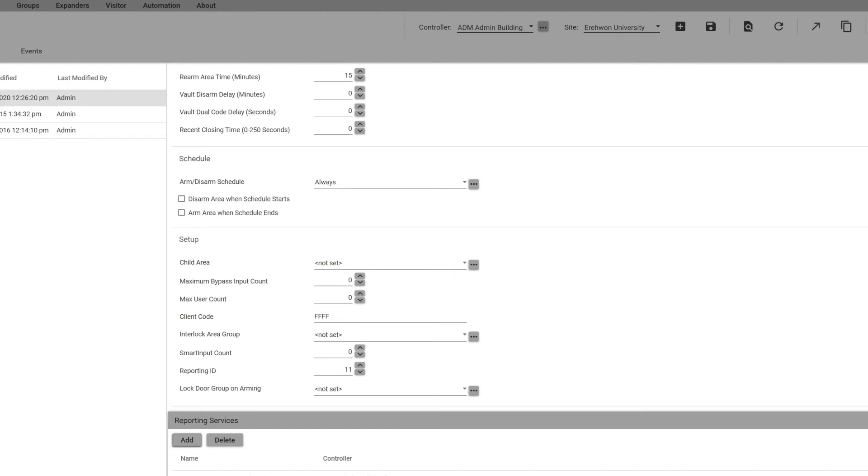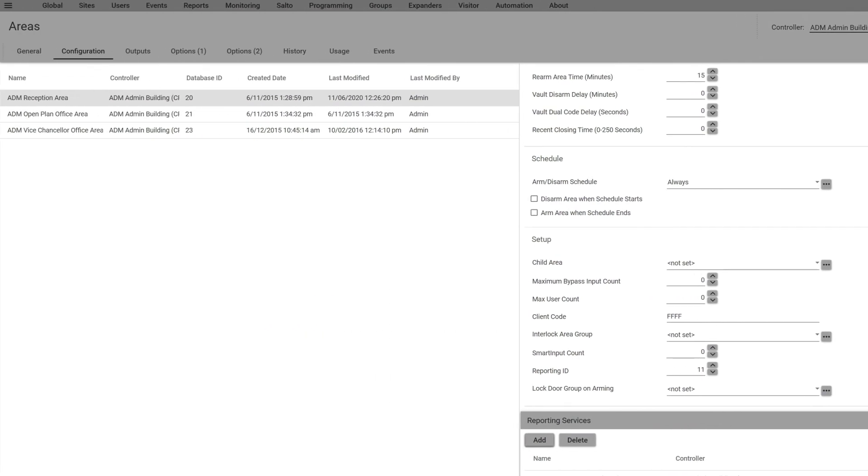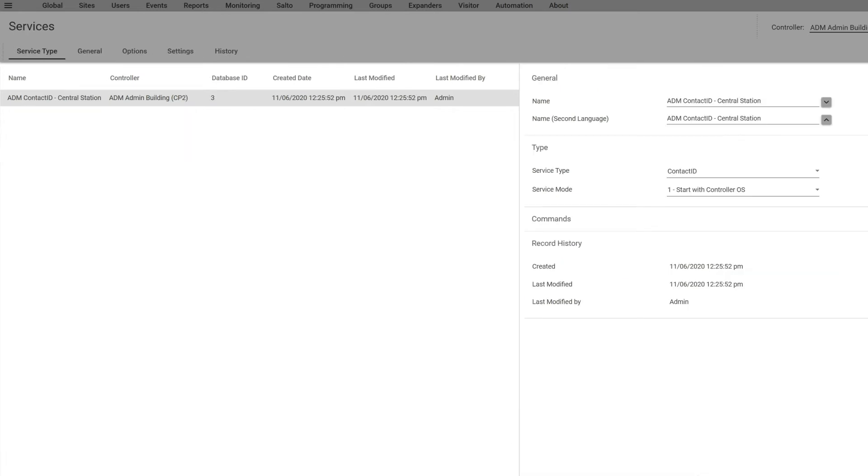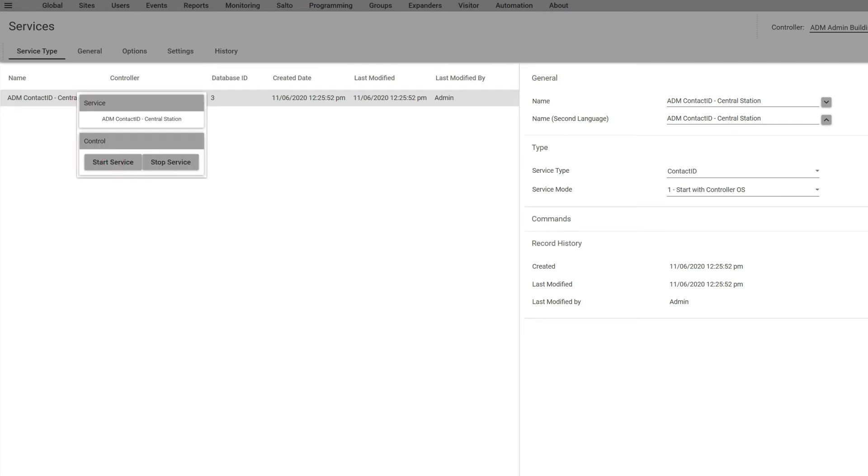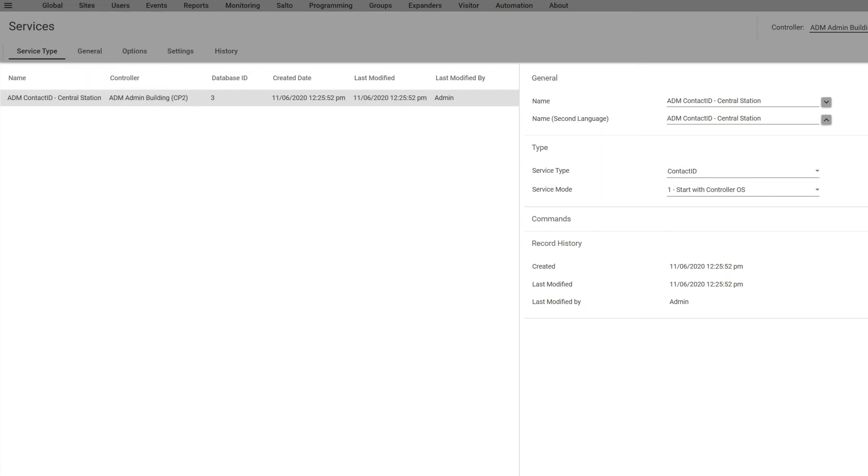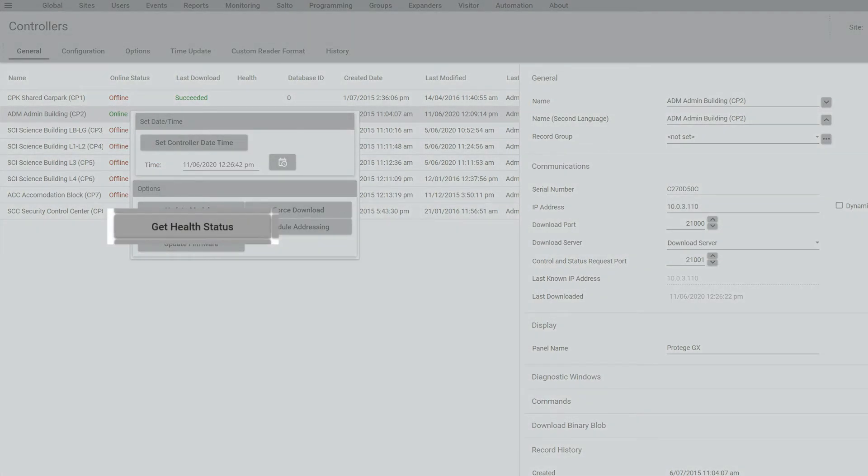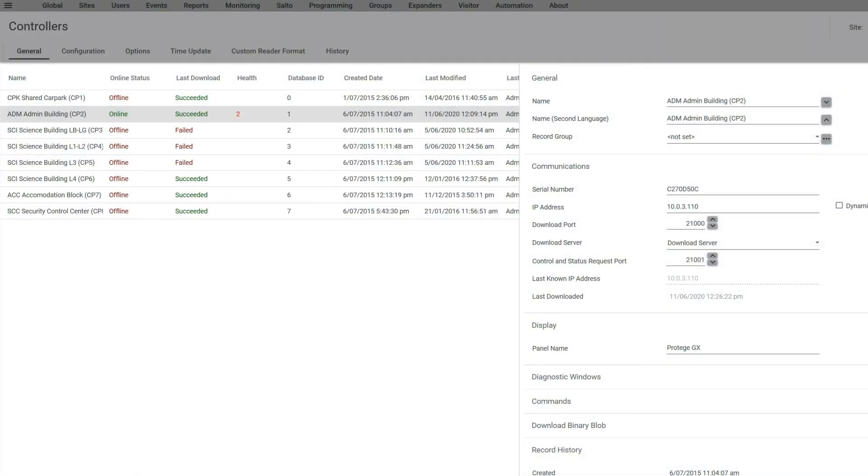I'm not completely done with this because I want to go back to my Services and you actually have to start your service. You have to right click on the record and say start service. Now if your service stops for any reason, a good troubleshooting suggestion is to go to Sites, Controllers and right click and see if there's any health issues relating to your service being off. If it's off obviously you want to restart that service. So that's for Contact ID, that's really basically the procedures to set up your Contact ID, not that hard.